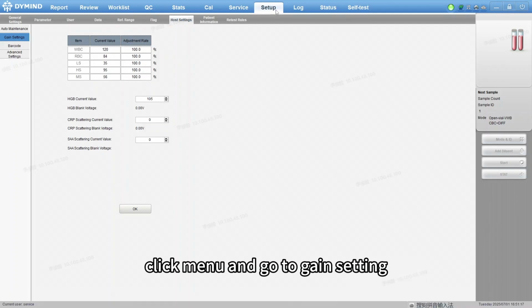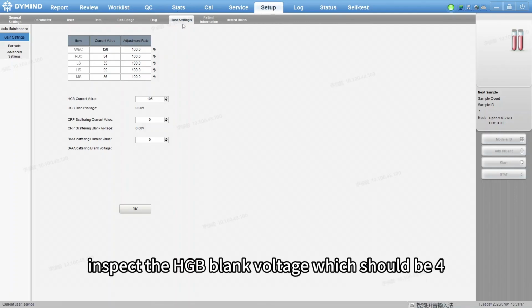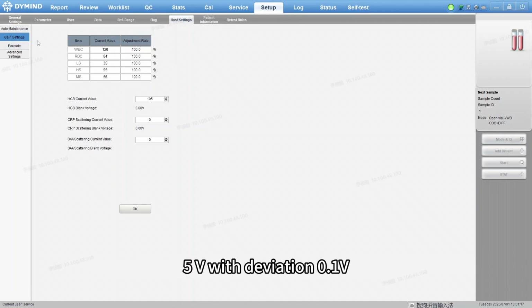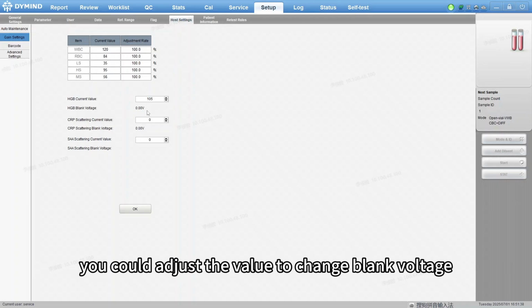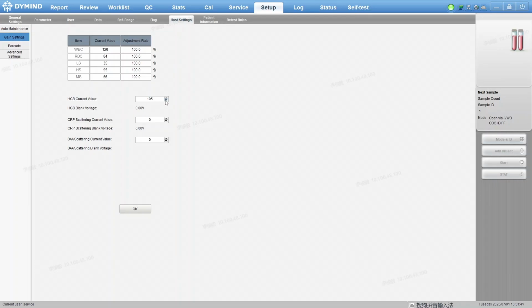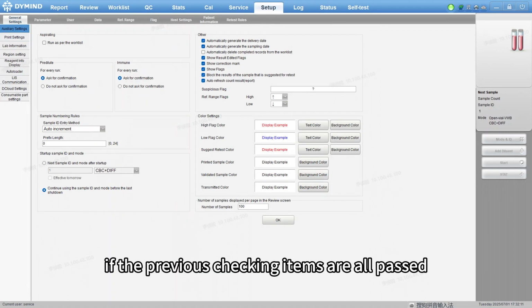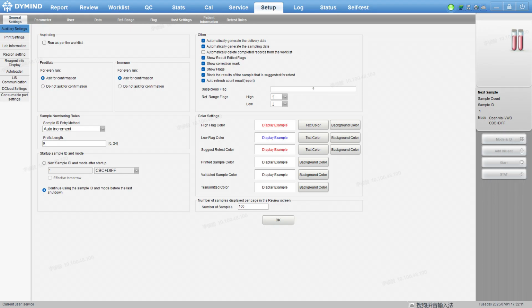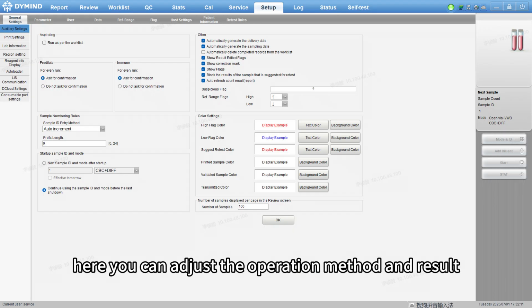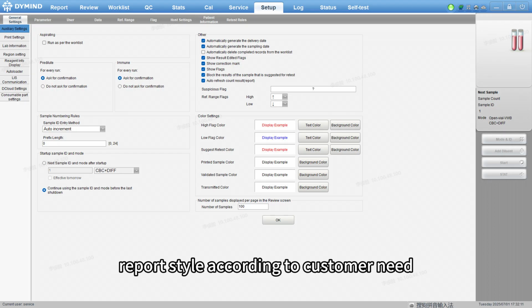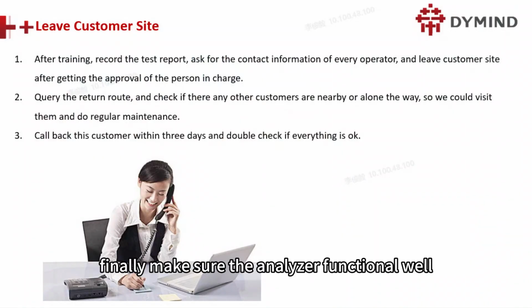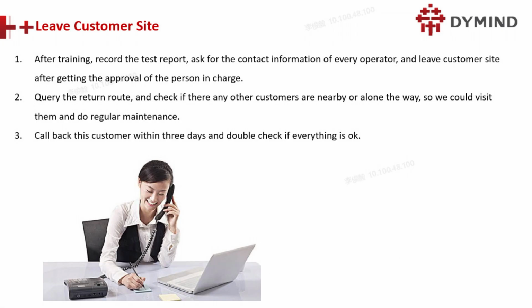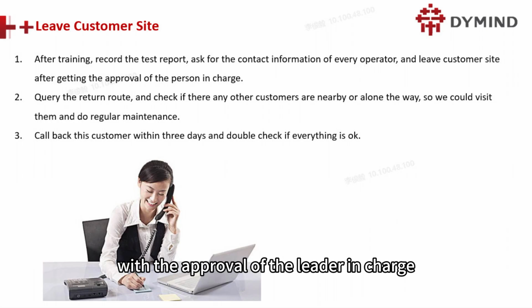Click Menu and go to Gain setting. Inspect the HGB blank voltage, which should be 5 V with a deviation of 0.1 V. You can adjust the value to change the blank voltage. If the previous checking items all pass, then it comes to the settings. Here you can adjust the operation method and result report style according to customer needs. Finally, make sure the analyzer functions well and the customers already know how to operate it. Then leave the customer site with the approval of the leader in charge.